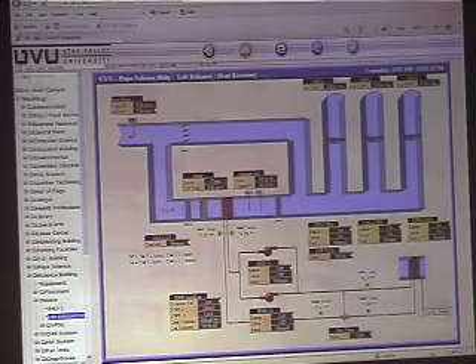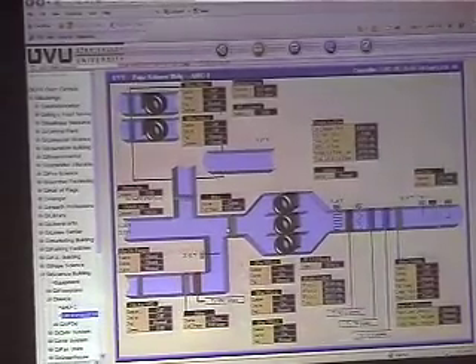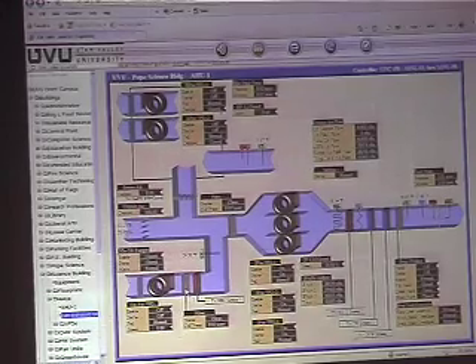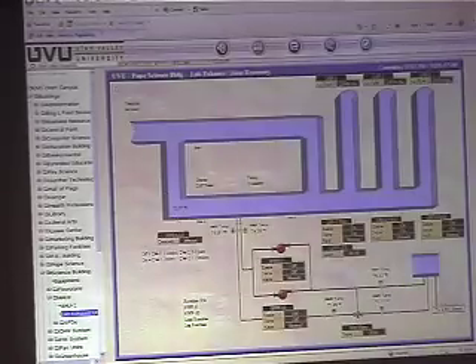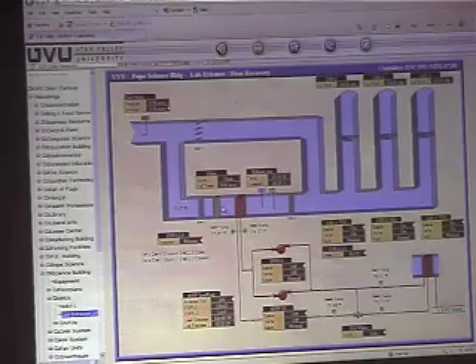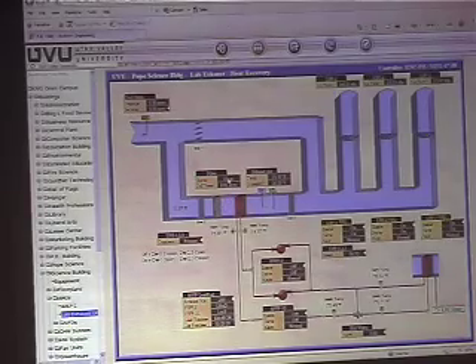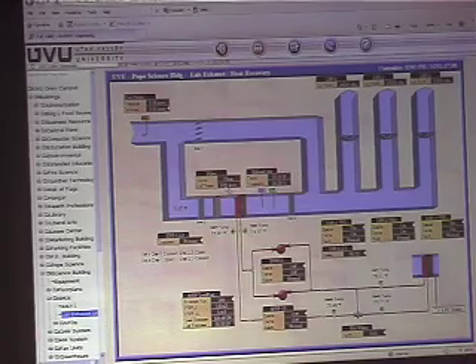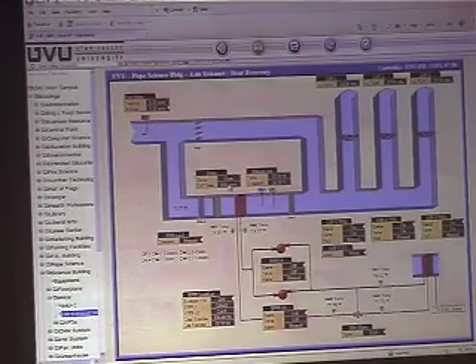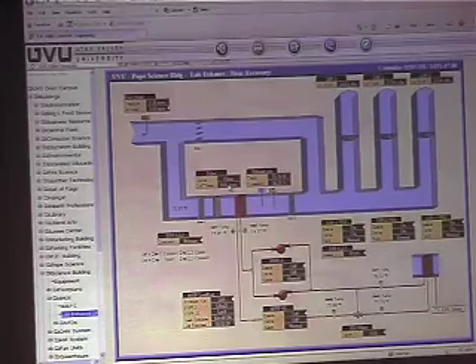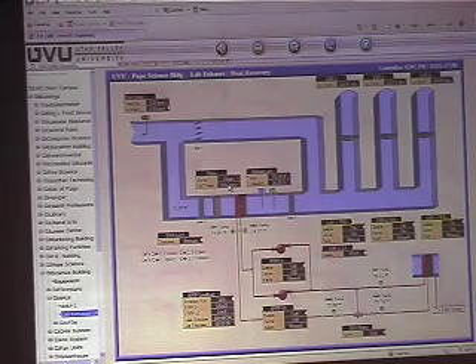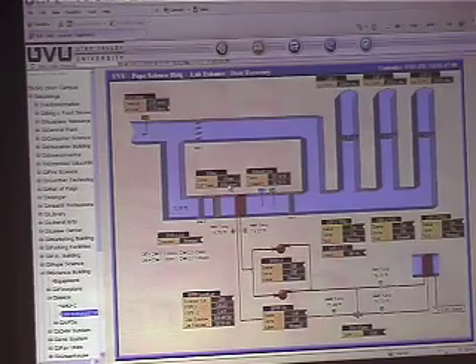Each of the filters, so let me go back to the air handler, I forgot to show you that. So there's a filter section here before the fans. There's one here before the heat recovery coil on the outside air fan, and then there's also one on the lab exhaust fans before this coil. They each have a clean or dirty status shown here, as well as your differential pressure. These units are so big, your differential pressure on your filters is really low. So you're looking at closer to 0.2, 0.4 for a dirty filter status, whereas you'd normally be used to something closer to 0.7, 0.6.